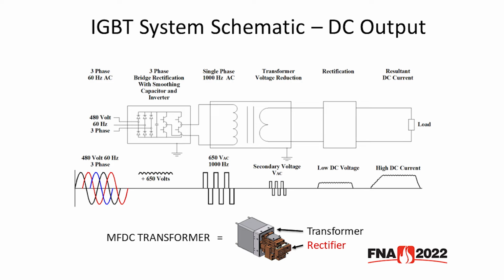This is then distributed to the MFDC transformer and stepped down to low voltage, high current power. Within the MFDC transformer, there are diodes that then rectify the 1000 Hz AC waveform into high amperage direct current output. This DC current is then delivered to the load.